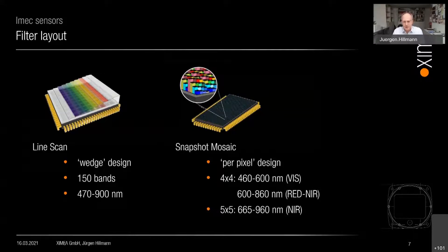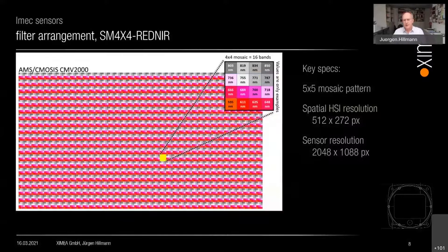With the snapshot sensor, one image delivers a complete hyperspectral imaging data cube. Three different standard sensors are available: a four-by-four pattern from 460 to 600 nanometers in visible light, another four-by-four from 600 to 860 nanometers covering red to near-infrared, and a new five-by-five sensor from 665 to 960 nanometers. This pattern is repeated over the complete sensor surface. The trade-off is reduced spatial resolution, since this is a two-megapixel sensor split across both spatial directions.